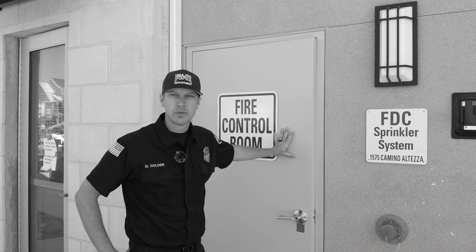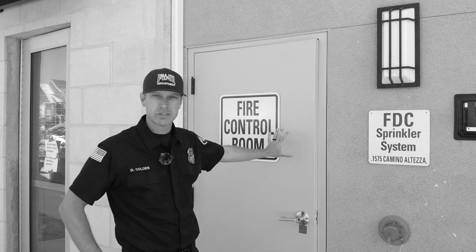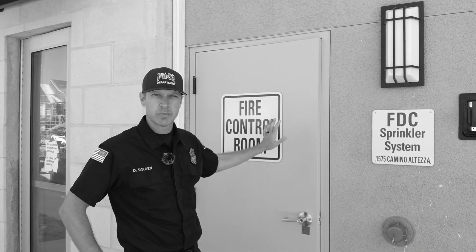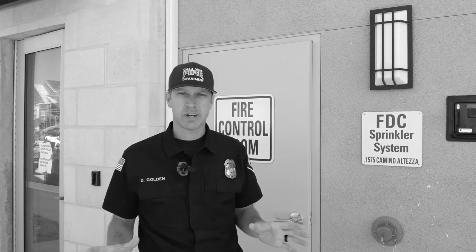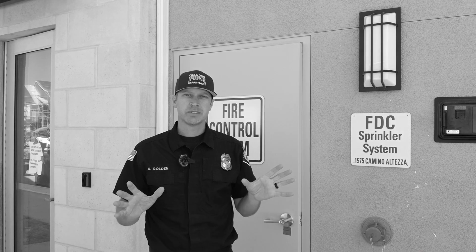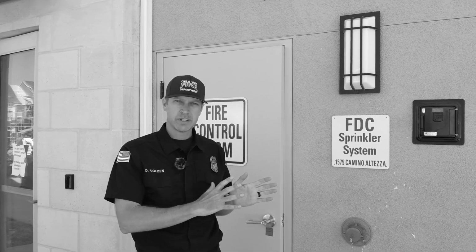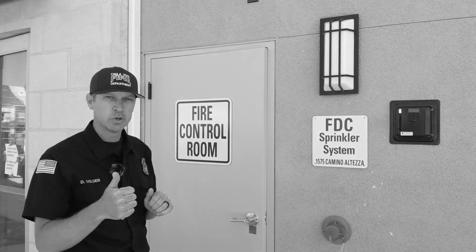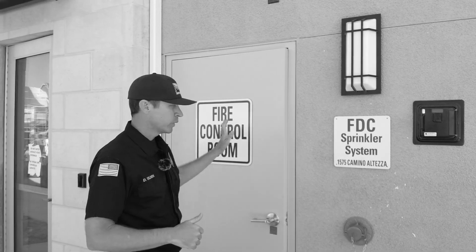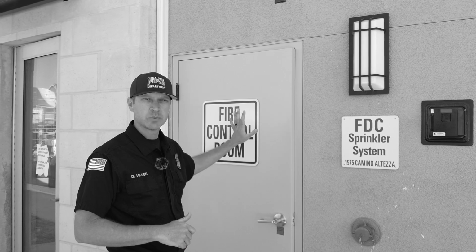If there is a fire control room, that means you're going to have your system riser, sprinkler riser, and your fire alarm panel located inside the room. So outside of a building actually on fire, or people screaming that the building's on fire, it's just a water flow event where we have a sprinkler flowing per our notes in CAD. We want to locate the fire alarm panel and the sprinkler riser.